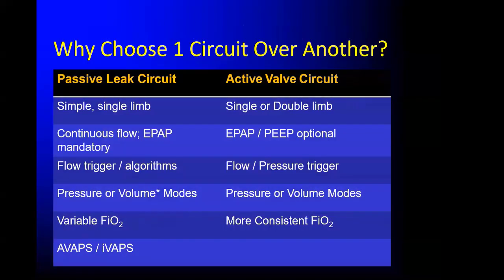So why choose one circuit over another? Well, I mentioned the simplicity of a passive leak circuit. The active circuit will be either a single or a double limb. Remember continuous flow, and that you have to use an expiratory pressure with a passive leak circuit, whether that's good or bad. Might make you decide one versus the other, because here PEEP or EPAP is optional. You've got choices with algorithms for your flow trigger with a passive circuit, whereas you only have flow or pressure depending on your machine with the active circuits.